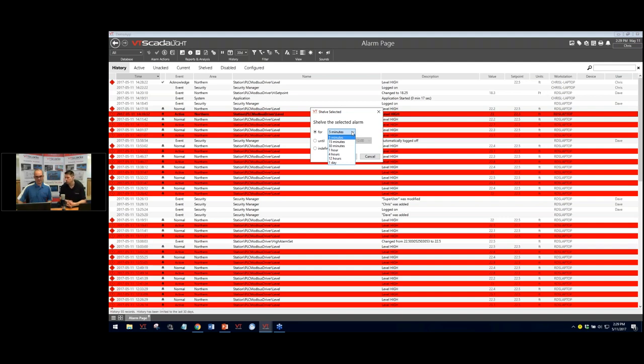Or if it's something that's going to be short-lived, then we can say do it for 5, 10, 15 minutes, whatever it is. So the shelving tool keeps the data, which allows you to go to your supervisor or whoever it is and have the data to back up that, yes, there is a problem, that this alarm didn't go off once every 5 seconds, three times. It went off once every 5 seconds all day. Right. But luckily, it didn't bother you once every 5 seconds while it was happening. That's right. So it's a way of reducing nuisance alarms so that real problems don't get hidden in maintenance issues like replacing PLCs. That's right, yeah.